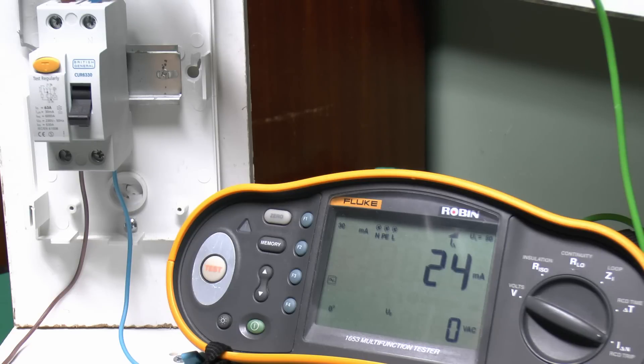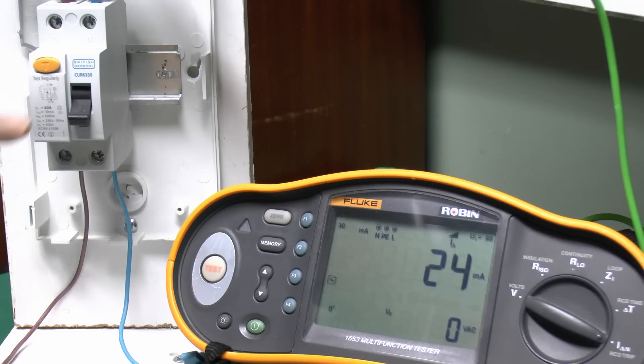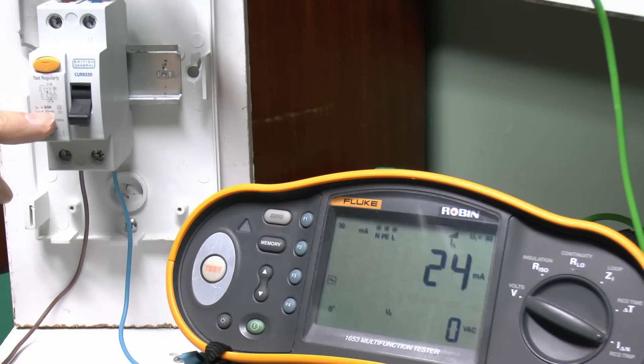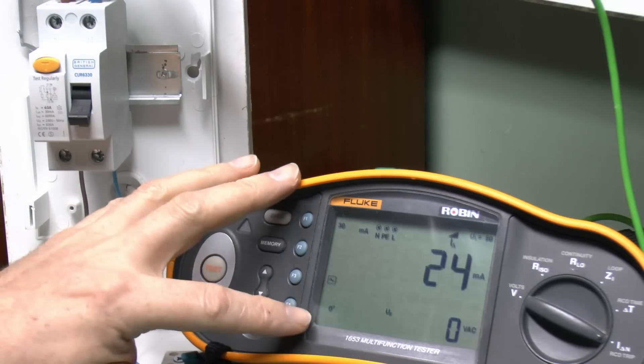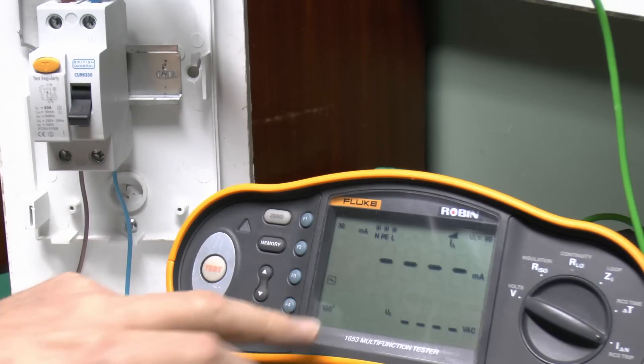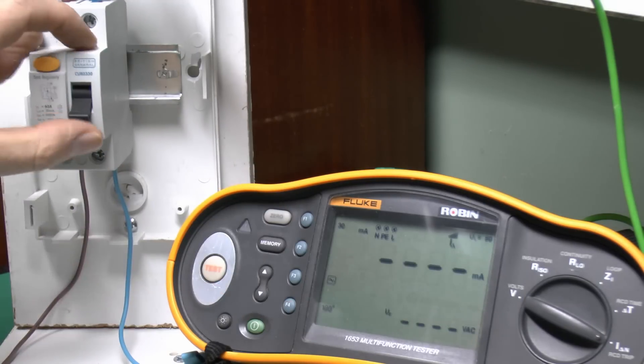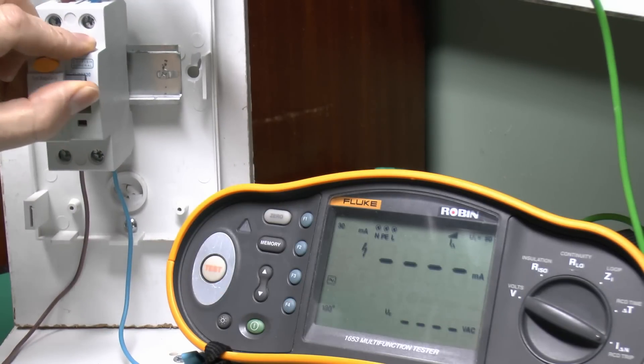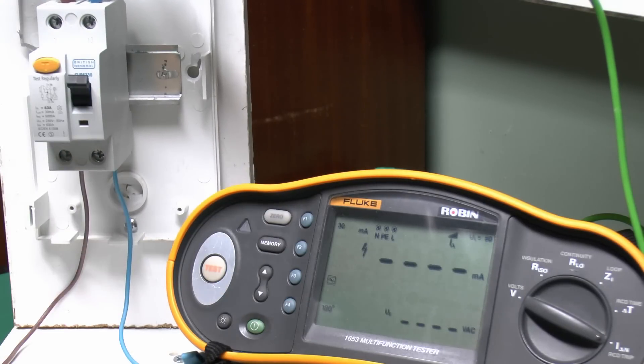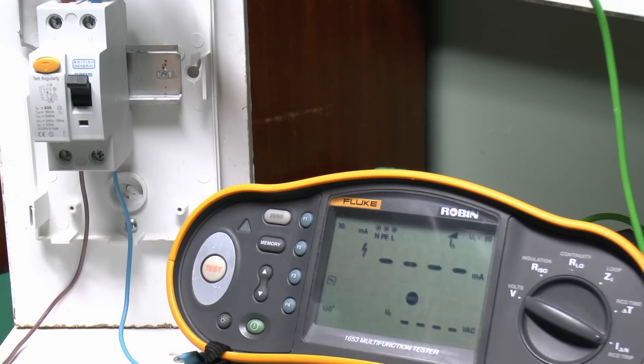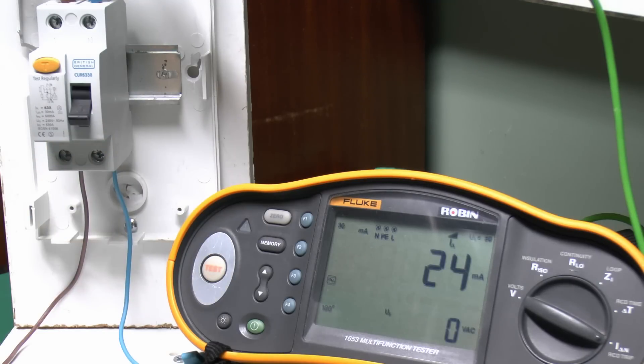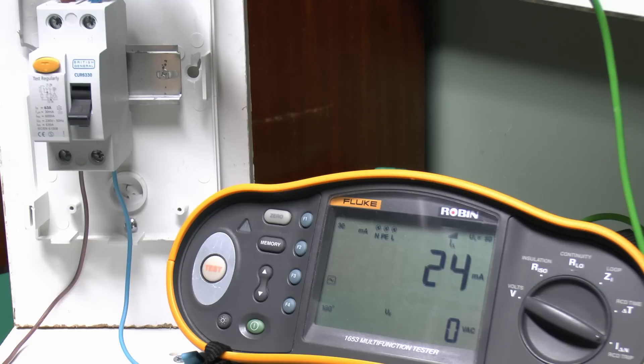Generally, you'd expect it to trip between half and the full rating of the device, so between 15 and 30 in this case, so 24, no problems there. Now, we should also do this test on the 180 setting as well. So again, we'll just switch on there, and again, it's the same, 24 milliamps. So that's a successful test for that.